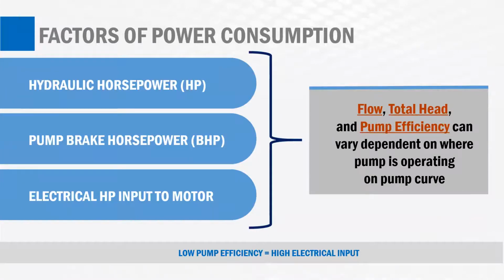So as far as power consumption is concerned, and I mentioned that's an issue, of course, what are the different factors that are associated with power consumption? First of all, just the hydraulic horsepower. It's important to take that into consideration. What that is, is it takes a certain amount of energy to move a certain weight of water at a certain flow rate against a certain pressure. But when you're looking at power consumption, you also have to take into account that there's a pump efficiency that has to be included in addition to a motor efficiency. And typically what happens with these systems, if you're looking at power consumption, the real varying factors tend to be flow, total head, and pump efficiency. These are all things that are seen on the typical manufacturer's pumping curves.